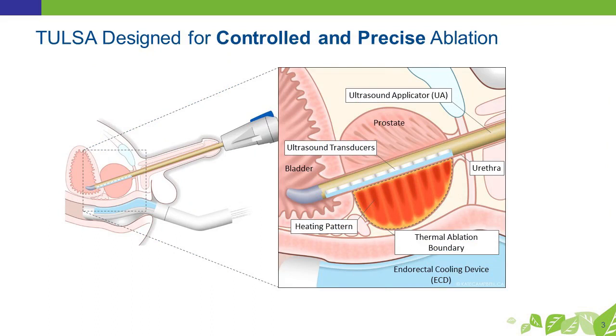So the components consist of the transducer you see here. It looks a lot like about an 18 French urethral sound with a flexible tip. It goes in over a guide wire, and it has these 10 5-millimeter transducers that are arrayed along a 5-centimeter length, which really is the length of most prostates. As the energy is delivered to the prostate, you see on the MR map a temperature change, and as the temperature increases in the irradiated tissue and approaches the predefined target boundary, the energy is controlled and stopped in that individual plane when the thermocline reaches the boundary.